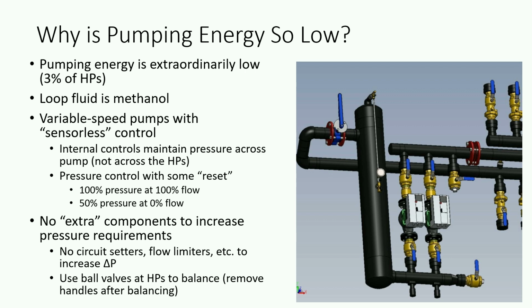The other thing is this controller also has a reset pressure, just like in a VAV system with air, where sometimes you might reset your pressure set point as you have lower load. You don't need the highest pressure. You only need the highest pressure at design conditions. You can probably get away with less pressure. This had a reset where it could provide 100% of the pressure differential at full flow. It drops down to 50% at low flow.